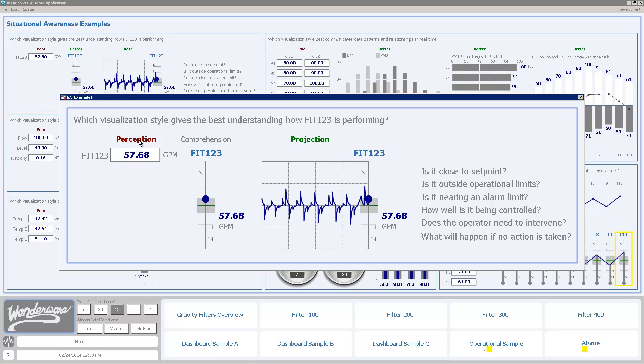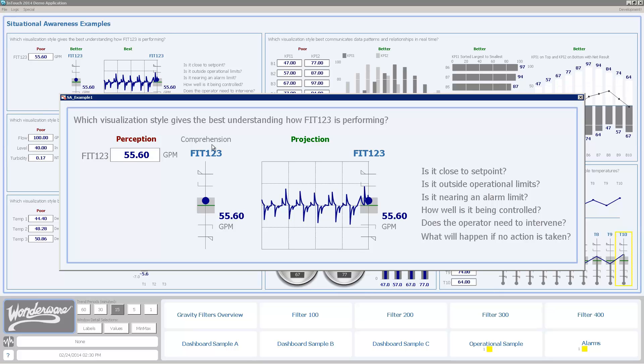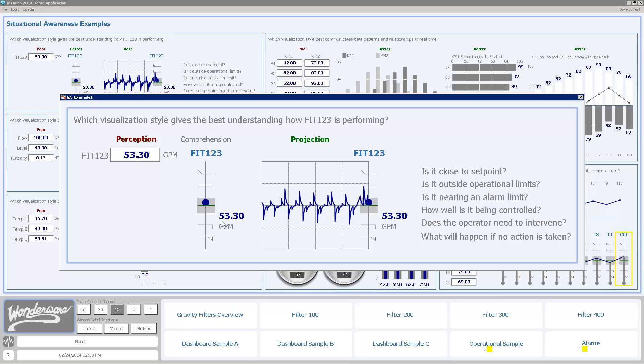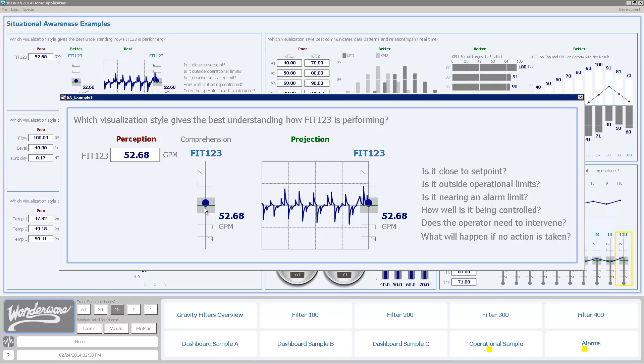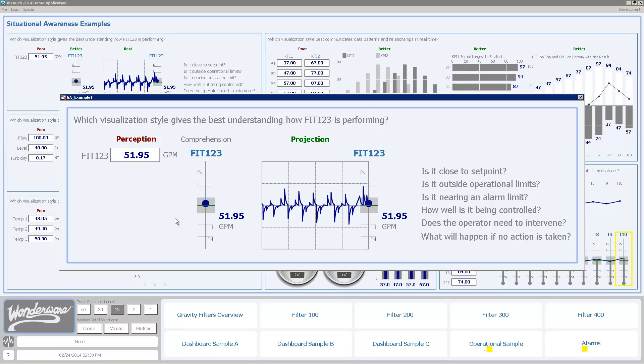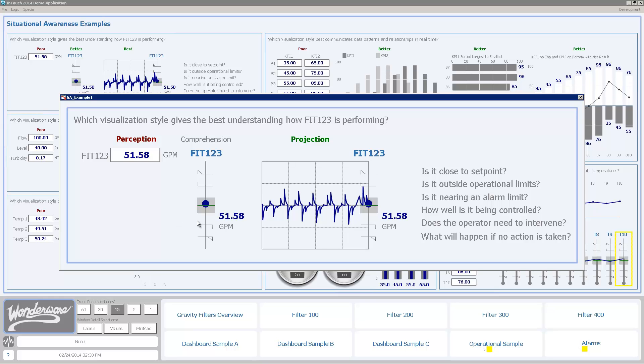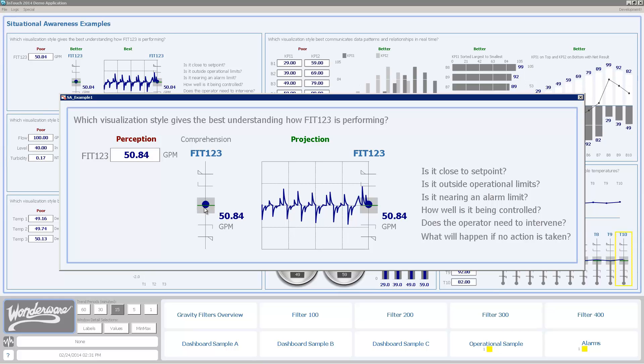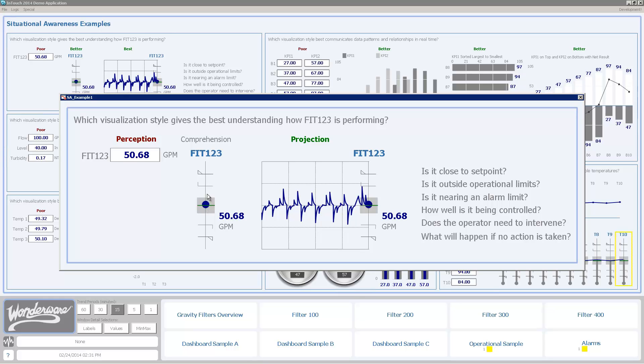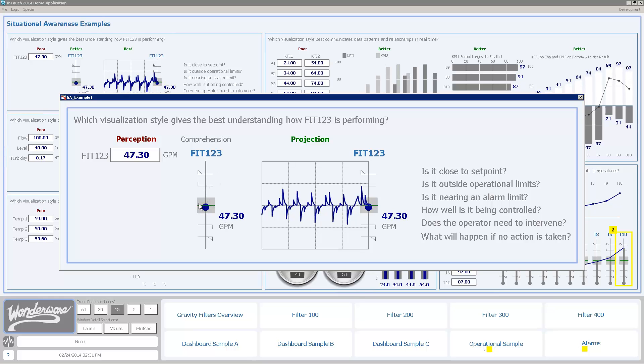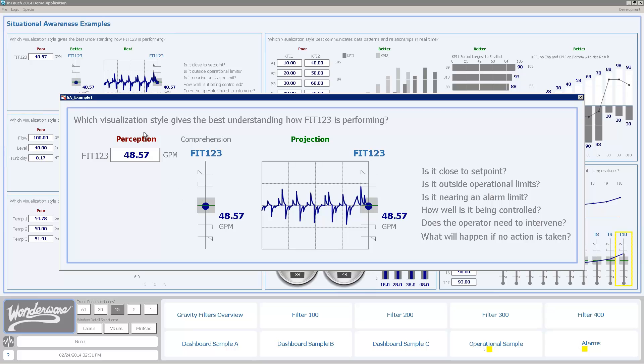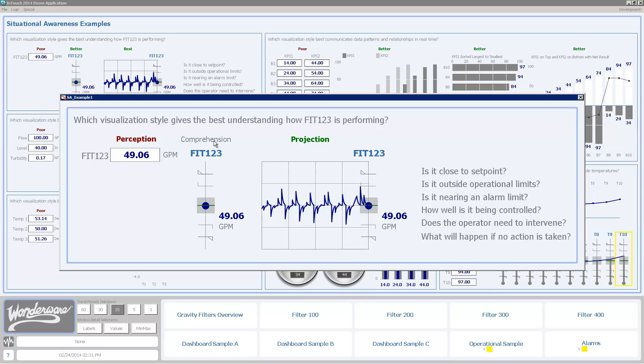Moving from perception up to comprehension here, where I have a meter showing this, I can see that the numeric value is still here, but now as I'm seeing this graphic next to it, I'm able to comprehend what it means a little bit better. Here I can see that the green line is my set point. I'm currently slightly above set point and I'm moving down. I can see this thing moving down, but I'm well within my alarm limits. I'm within the expected operating range as well. So here I've gained more than just perception, but also comprehension, a little bit more of the meaning.